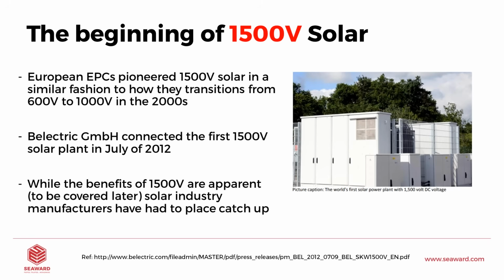So certainly that's why we're putting them in the designs of solar plants, but we're not necessarily seeing the equipment catch up with those designs. And that is certainly true in the test instrument arena. For instance, right now, our Solar Utility Pro is one of the only 1500 volt solutions out there. It's certainly the most cost effective. There are others. There are one or two curve tracers out there, but they're very, very high in value, and some have not been released yet and are scheduled for release in May, and a little bit more on that later.